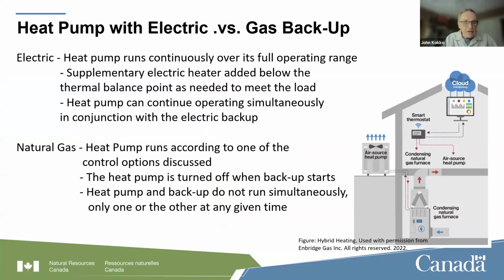So we are talking about heat pumps with backup. Now, backup can be electric or gas. And with an electric backup, the heat pump will run continuously over its full range of operation. So if it can go down to -30, then the heat pump will run down to -30, and the electric supplemental heat will come on when it's needed to maintain the load in the house. But the heat pump does continue to operate, and so the two are running simultaneously.